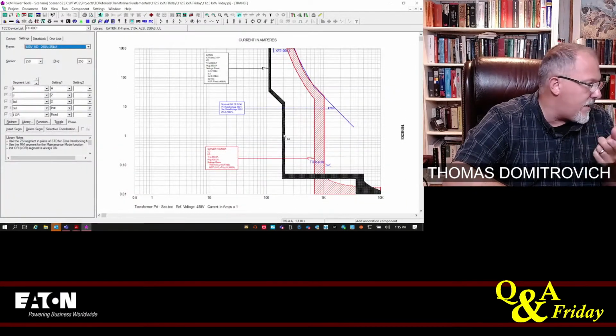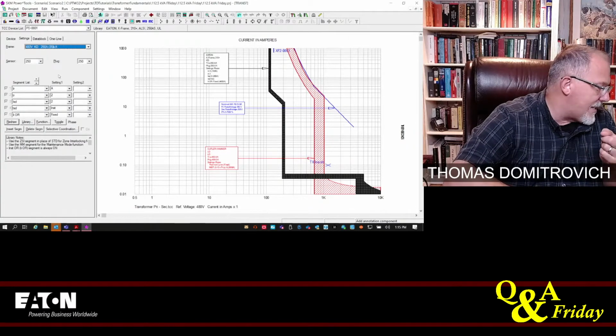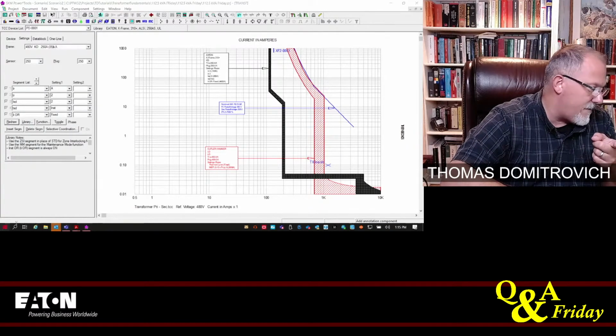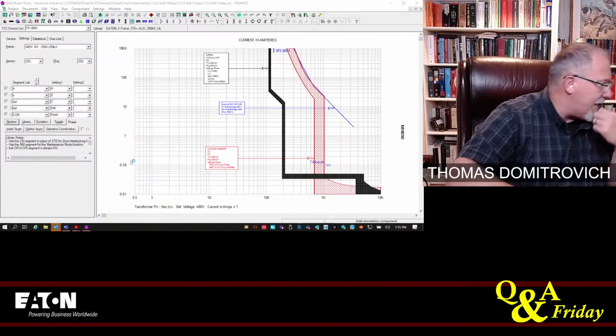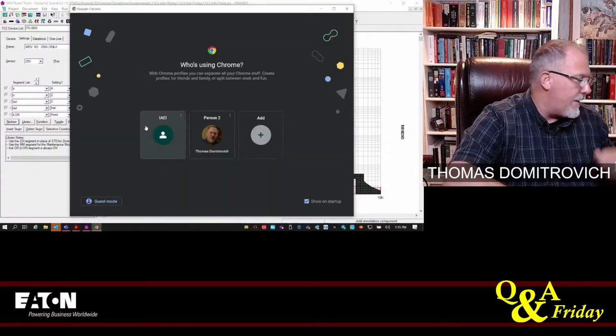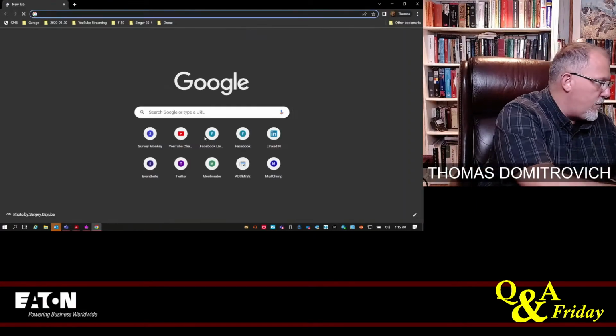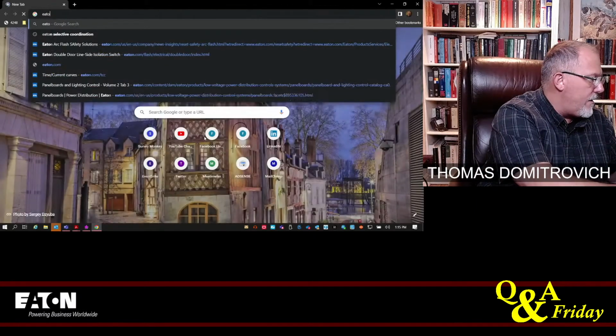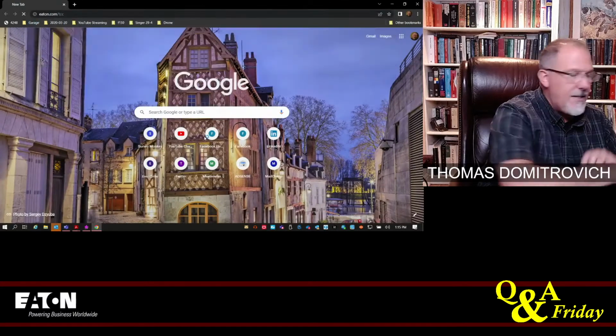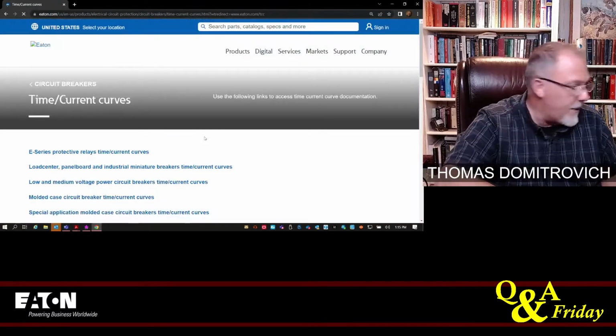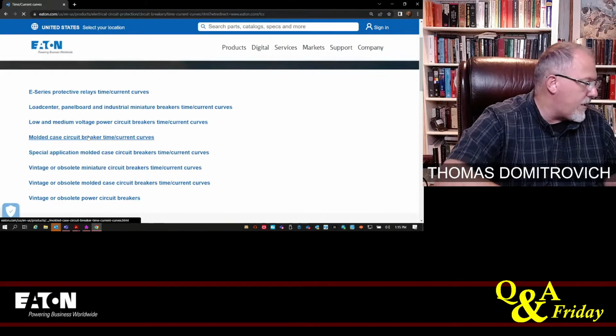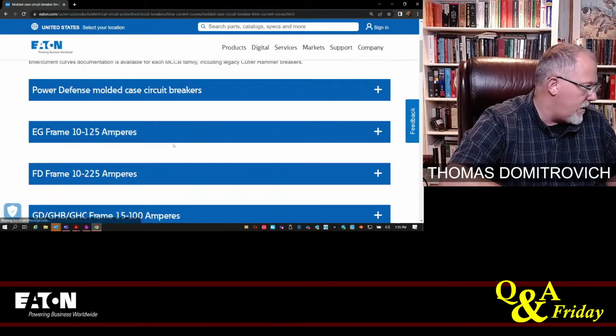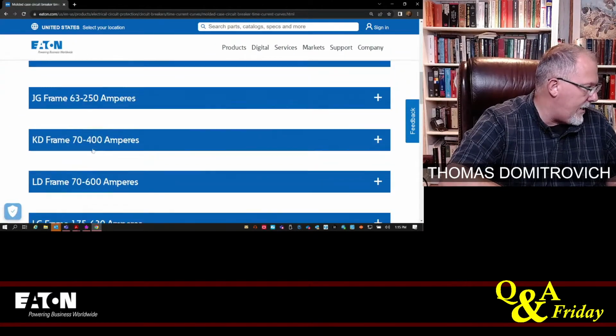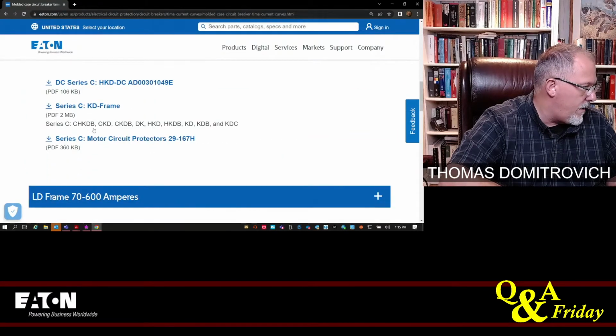So this is a KD breaker. I've got to figure out my settings for a KD with a 310+ trip unit. So here's what we'll do. We will go to eaton.com/TCC for time current characteristic curves, go to molded case circuit breakers, and we will go to a KD breaker, Series C.